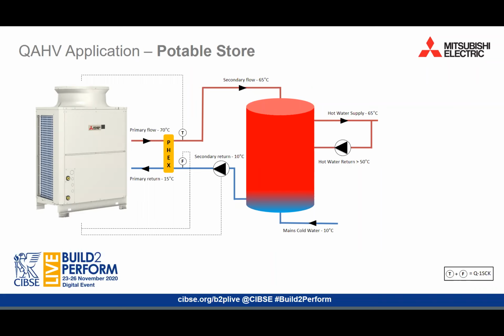So as we've discussed, we need to maintain as low a return temperature condition as possible. When the return water temperature to the unit is higher than 29 degrees, we see an undesired capacity reduction and COP loss. Now, this can be acceptable in the later stages of a vessel heat-up cycle as the temperature in the vessel is increasing to the desired storage temperature, but it is certainly undesirable to be happening all of the time. We need to provide an indirect hydraulic solution. This is needed to protect the heat exchanger in the QAHV against poor or hard water quality, which could result in scaling and corrosion issues. And for projects where there is large peak usage, for example, a hotel or student accommodation, it would be suggested to have a store of potable hot water to meet the peak periods, like the example shown here.